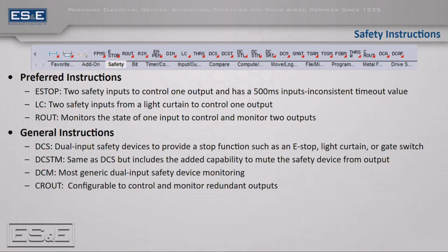The same is said for the R-out and CR-out, which stands for redundant outputs and configurable redundant outputs. So when you add that extra configuration, it just adds one layer that you need to validate and verify to make sure your system is okay, whereas the redundant outputs removes a little bit of that burden on that specific programming instance that you have.